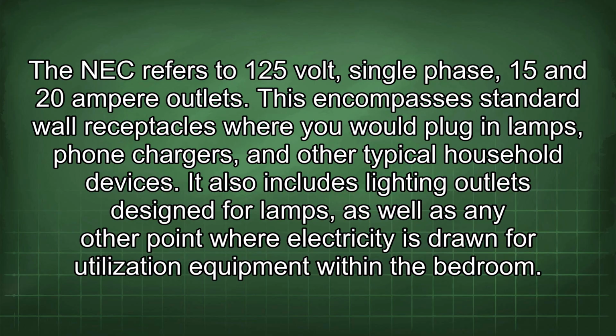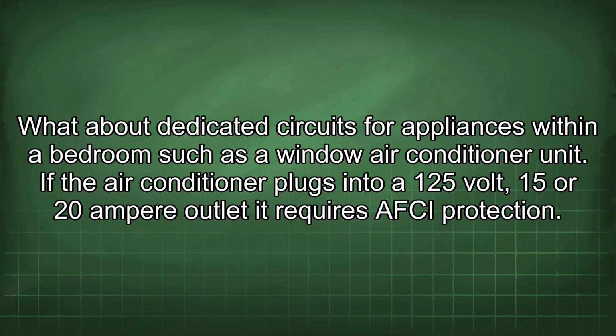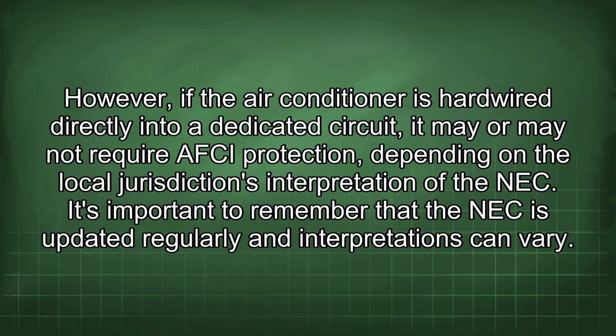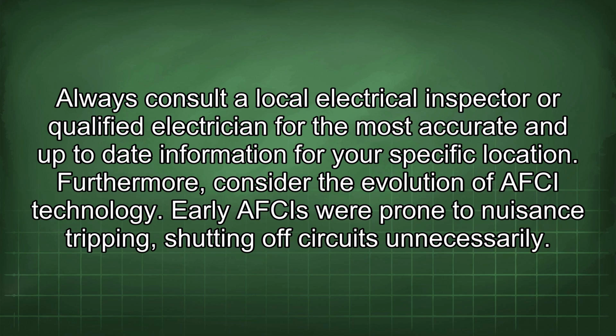What about dedicated circuits for appliances within a bedroom, such as a window air conditioner unit? If the air conditioner plugs into a 125-volt, 15 or 20 ampere outlet, it requires AFCI protection. However, if the air conditioner is hardwired directly into a dedicated circuit, it may or may not require AFCI protection depending on the local jurisdiction's interpretation of the NEC. It's important to remember that the NEC is updated regularly and interpretations can vary. Always consult a local electrical inspector or qualified electrician for the most accurate and up-to-date information for your specific location.